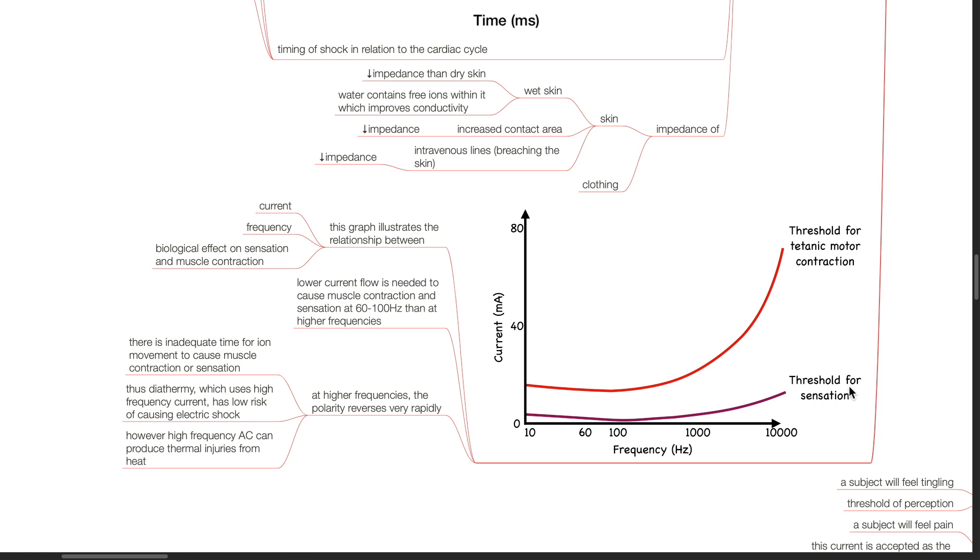This graph illustrates the relationship between current, frequency and the biological effect on sensation and muscle contraction. Lower current flow is needed to cause muscle contraction and sensation at 60 to 100 Hz than at higher frequencies. At higher frequencies, the polarity reverses very rapidly. There is inadequate time for ion movement to cause muscle contraction or sensation. Thus, diathermy which uses high frequency current has low risk of causing electric shock. However, high frequency AC can produce thermal injuries from heat.